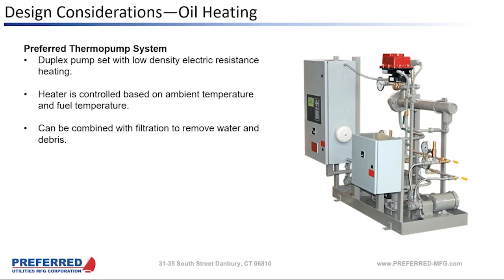I think that's a great idea. And one of the things that we tweaked here in the Northeast, because we've done it that way for a while, is in a lot of the newer designs that we're doing with firms, you mentioned the 3-way valve there. I think historically it was very common to use a 3-way valve to allow circulation back to the main tank rather than sending fuel up the riser to one or more day tanks. One of the modifications that we've made after meeting with different firms and looking at single points of failure is that we've modified that to a full circulation loop.